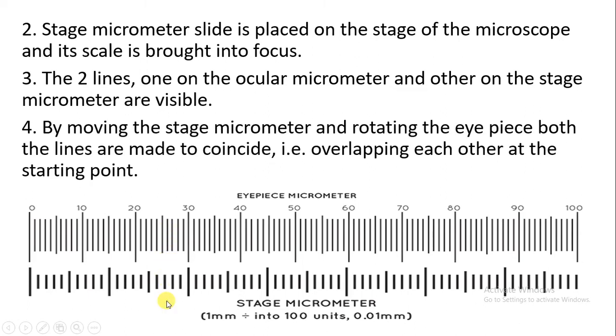Both the lines should be visible. The ocular micrometer is rotated carefully so that the lines of the stage micrometer and ocular micrometer coincide or overlap. The starting point — the 0th line of the ocular micrometer should coincide with the 0th line of the stage micrometer. Then the next line that coincides is identified — we look for the next division where both lines overlap — and we record the stage divisions and ocular micrometer divisions.